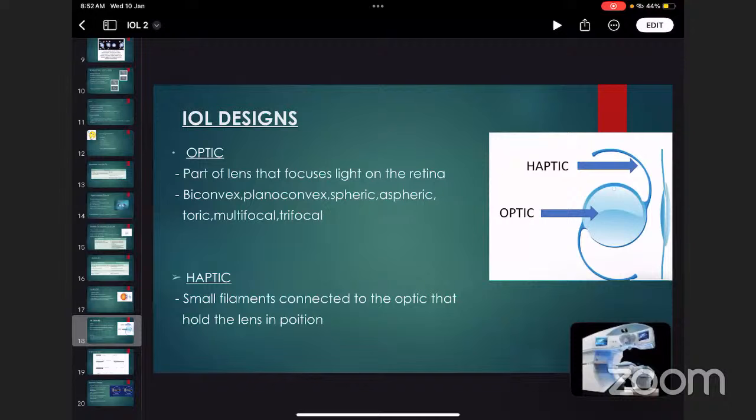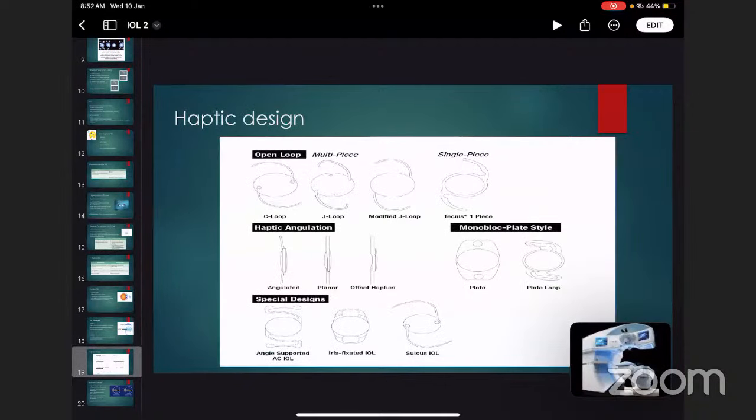IOL design: IOL is distributed as optic and haptic. Optic is the part of the lens that focuses light on the retina. There are multiple designs: biconvex, planoconvex, spheric, aspheric, toric, multifocal, and trifocal. In the haptic: small filaments connected to the optic that hold the lens in position. Different haptic designs include open loop with C loop, J loop, modified J loop, plate style, and angulated haptics.